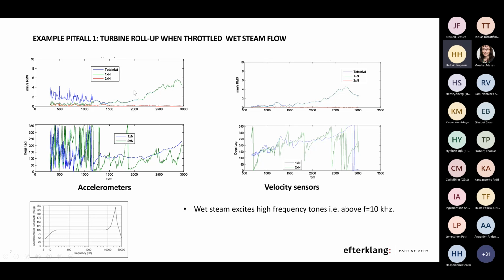Then the total level is controlled by the natural unbalanced forces at one times the revolution. And what's happening here? The steam will excite the high frequency, and when you use accelerometers, you know that they are linear up to a certain range, and then they have a very high resonance peak. So in this wet steam flow, you excite and overload the sensor. To work around this, they changed to a velocity sensor, which is less susceptible to high frequency noise, and they got the run-up working for the full speed range.